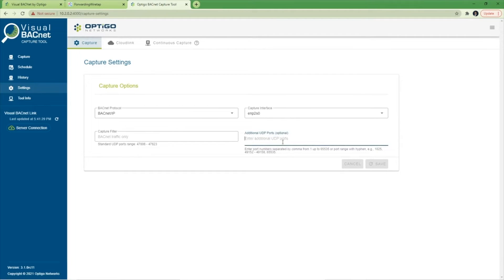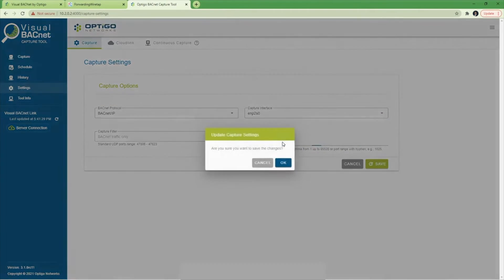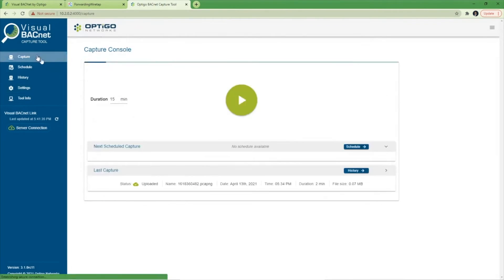If you have BACnet data on other ports, enter them here separated by commas. If you're using the Jace wiretap feature that's available to users of Niagara 4 and above, enter 49000 here. Click Save.